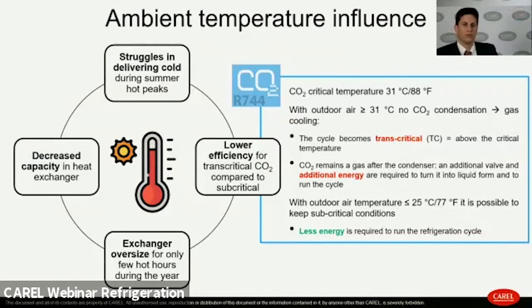One possible solution could be to oversize the heat exchanger. In this way, we can exchange more heat in critical conditions. Anyway, this solution is not really cost-effective, so it's not something we would suggest. Another solution could be to adopt a wet media evaporative cooler, but again, it is not something that I really recommend, since wet media is installed in front of the heat exchanger, and it will cause pressure drop to the air that is incoming inside the heat exchanger. So the energy consumption is not really optimized in this way again.